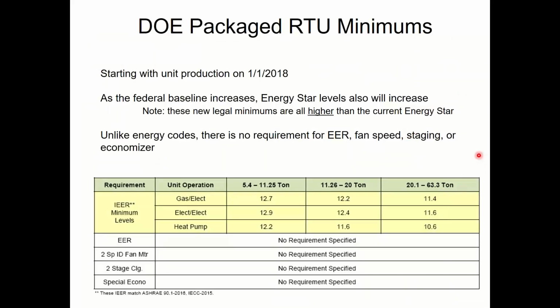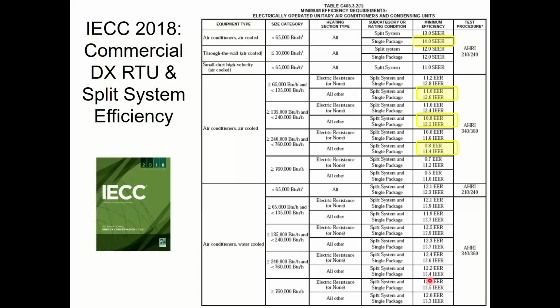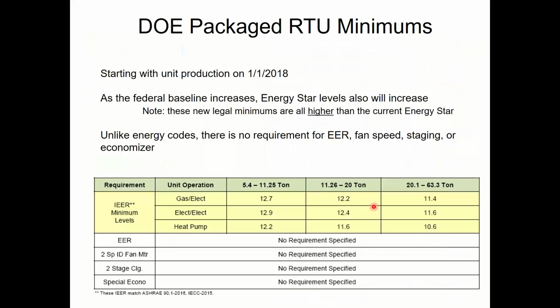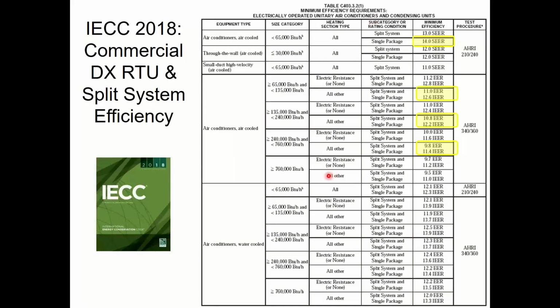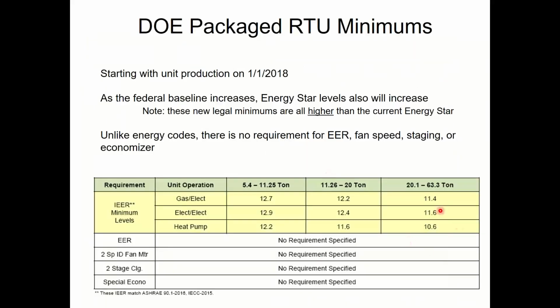The Department of Energy also has its own minimums, so that's code minimums. Then the Department of Energy establishes minimums. Code minimums are policed at the local level by your code official. The DOE minimums are policed at the national level and at the manufacturer level. They're not allowed to build anything less than this. So if a manufacturer had built something less than this in 2017 and your distributor still had it laying around in inventory and it still complied with your local code, you could put it in, right? But they can't build any more after a certain date. In this case, 3 years ago, they had to build everything this good or better.